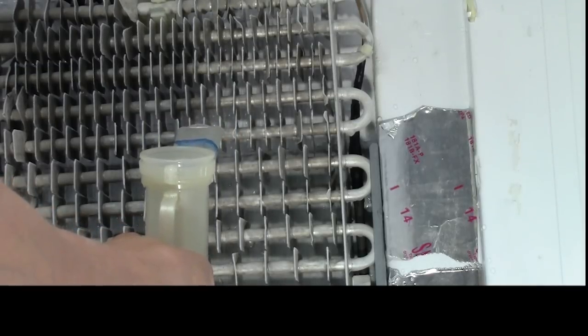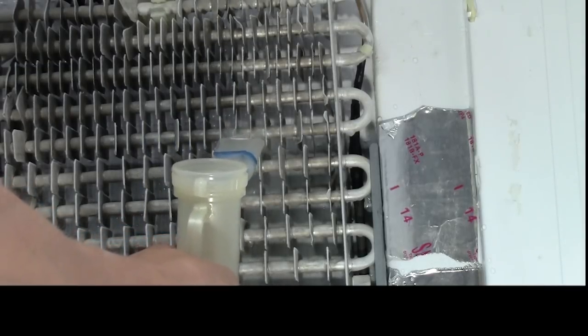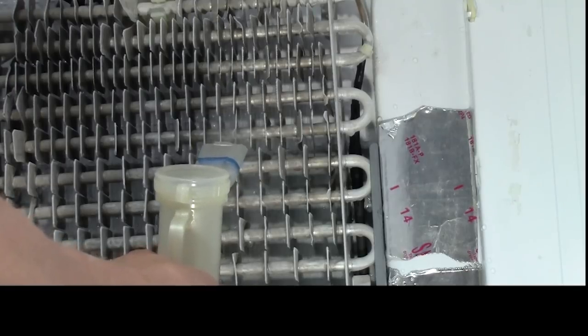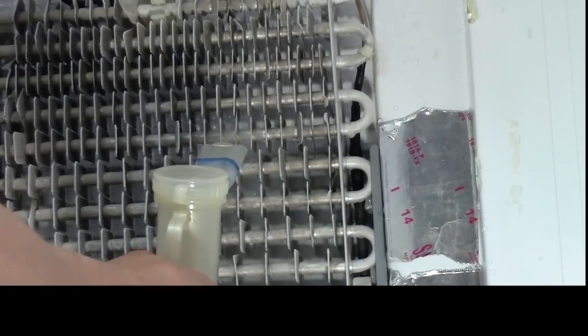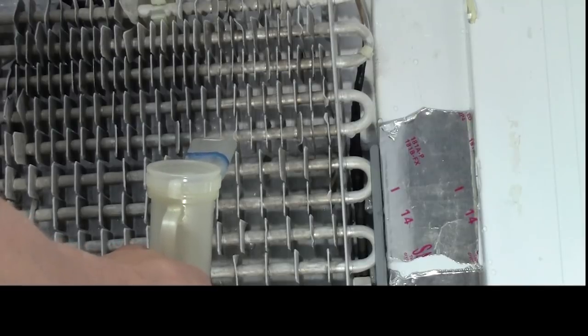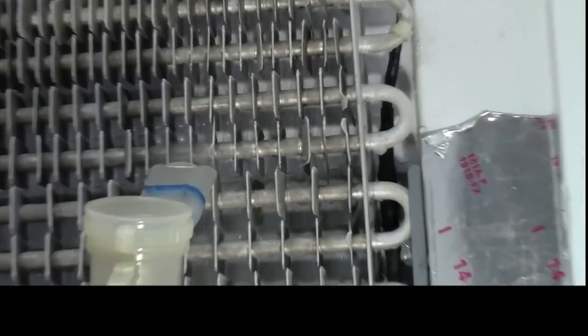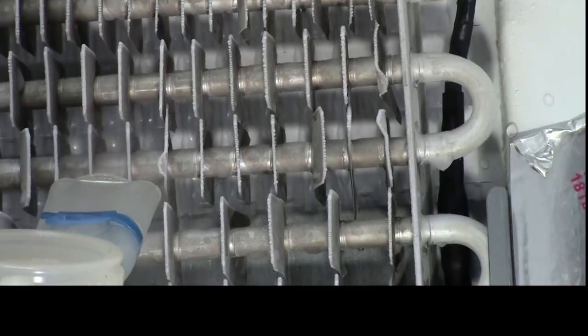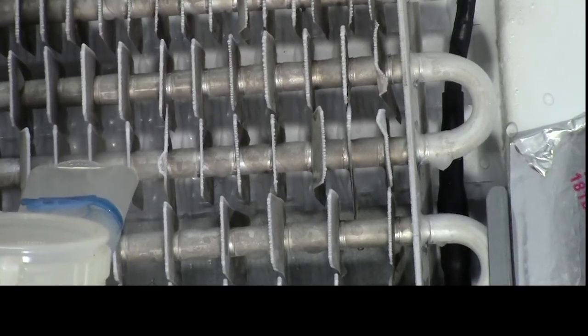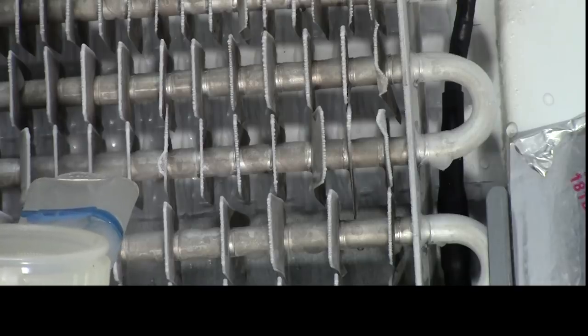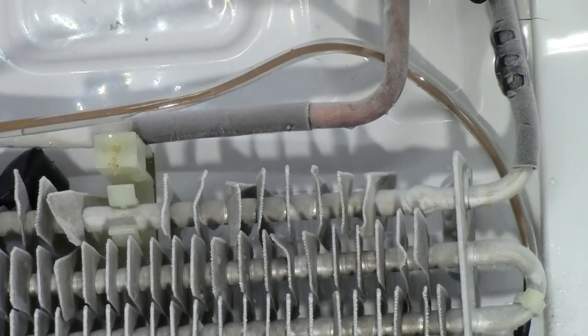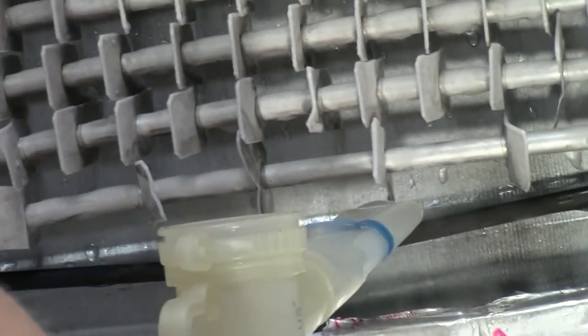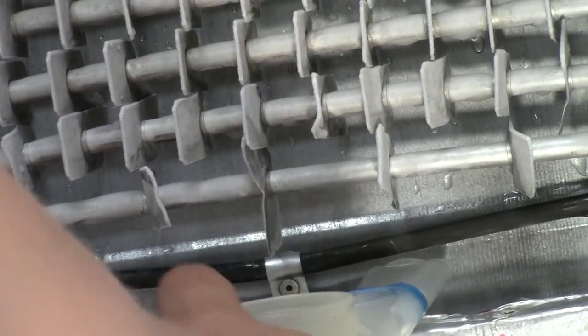That is that any amount of humidity or moisture in the air that passes over those coils while that machine is plugged in is going to freeze. Now that heating coil is supposed to melt the ice every now and then when needed. It has a little thermostat in there. What's supposed to happen is the cooling coil is supposed to shut off and the heating coil is supposed to kick on, and any amount of ice that has built up, if there is any, should defrost. It should drip down into the hole and be removed.